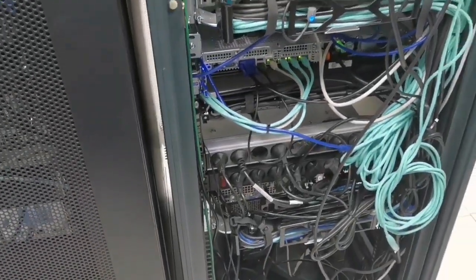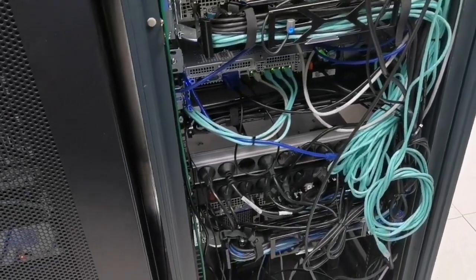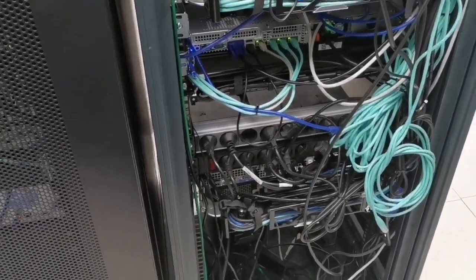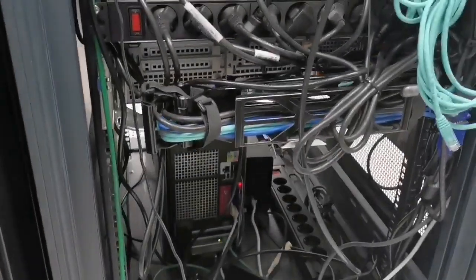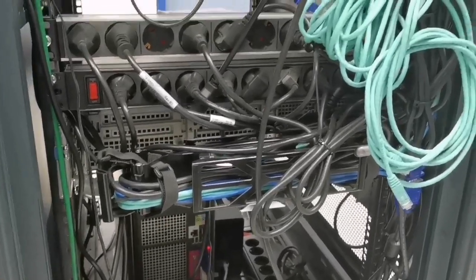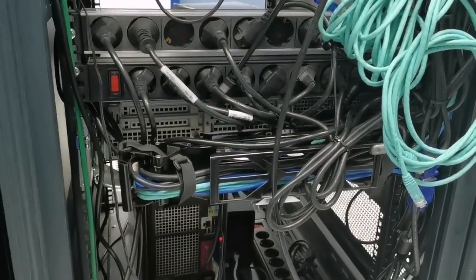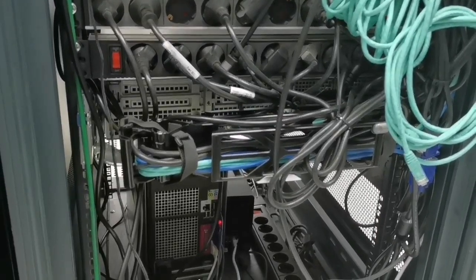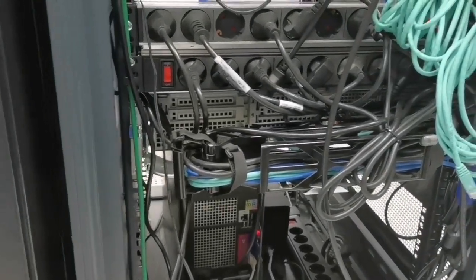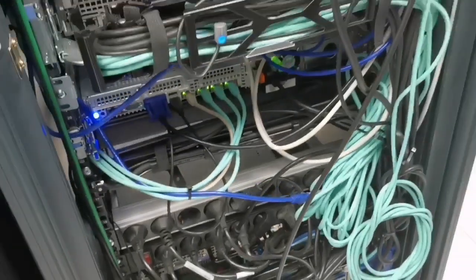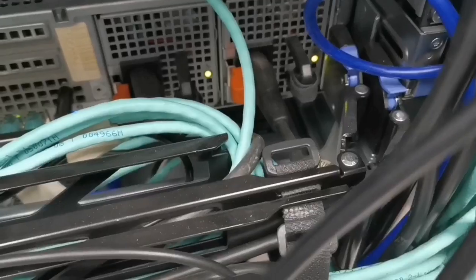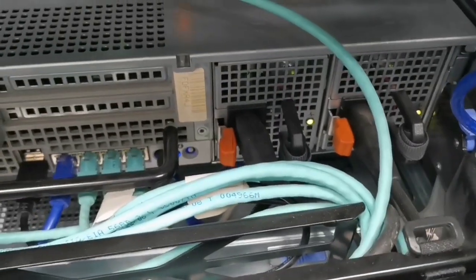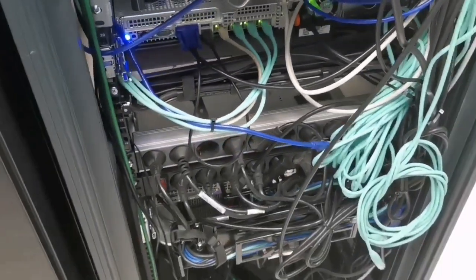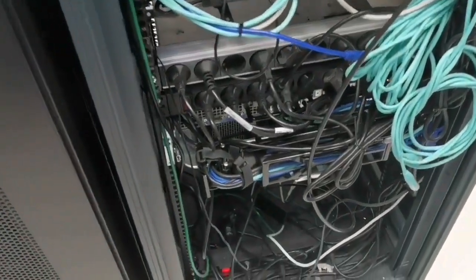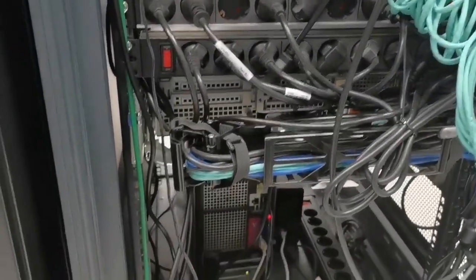The most important thing in the server room is the redundancy. The PDUs at each cabinet are connected to two power sources, and each server has two power supplies, each connected to a separate PDU. So that in case a certain power source failed, as you see here, we have two power supplies in the server. In case one of the power sources failed for any reason, the server will stay up and connected.